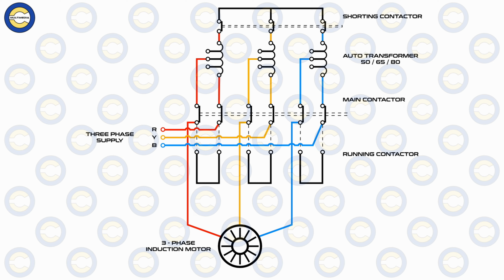So even in the fixed tapping design, you have the flexibility of adjusting the tapping during the maintenance and the open procedures. However, there is no control system that can do it without manual intervention. For example, if we have a high inertia load requirement, we might choose the 80% tapping, even for initial running in. Whereas for lighter operations, we have an option of choosing 50%.